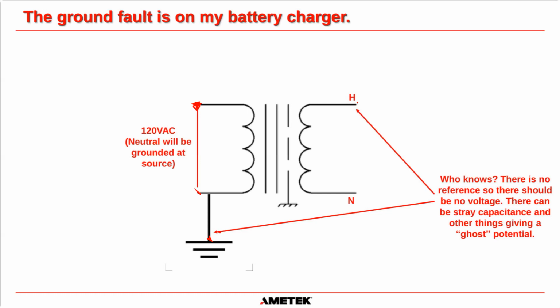What confuses a lot of people is that, because of stray capacitance in cables that are run all over the plant, and also some induction that happens between cables, there can be a weird voltage on a truly floating system. You could measure, maybe it would start off at 25 volts, but then you would see it gradually reduce. Basically, your Fluke or your multimeter is acting as a load on that stray capacitance and discharging it, and it will tend to go down to zero. But in truth, there is no reference.